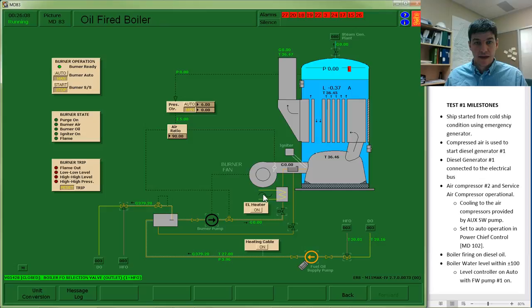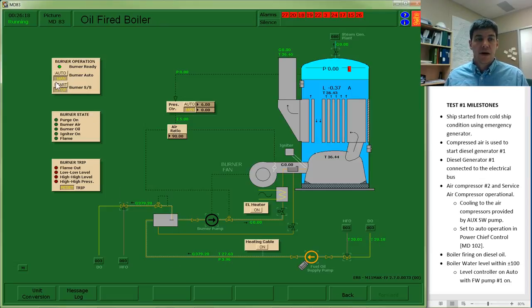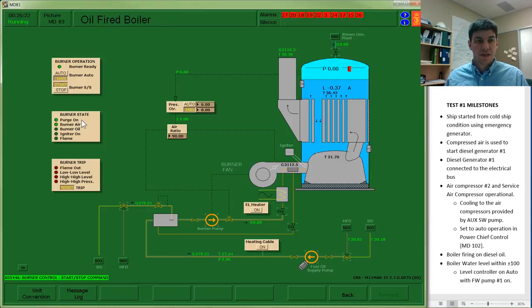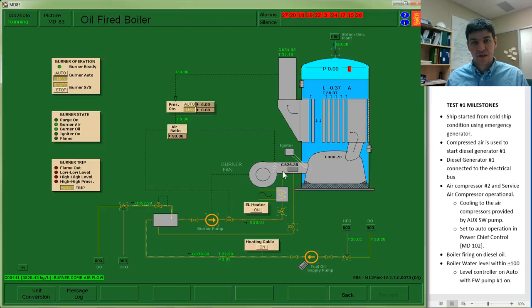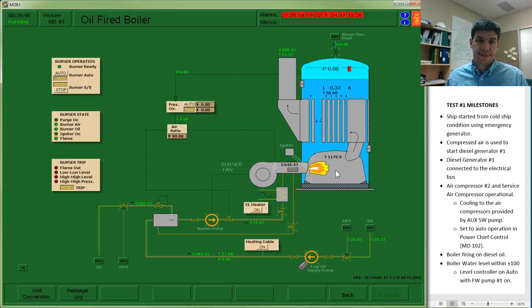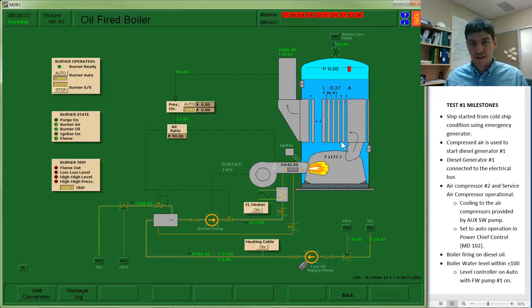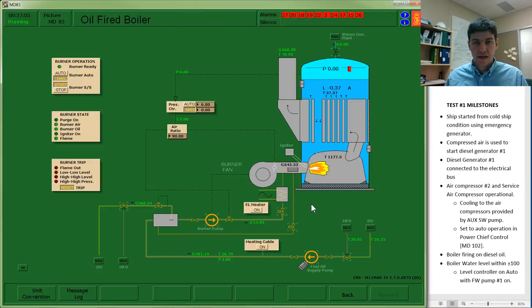Make sure when you're doing that that you don't have your heating cables on. Those are only used for the heavy fuel oil. Diesel oil doesn't require those cables on. So I hit start and it goes through, first of all, a purge process. And you can see that the flap just opened up on the fan and it's blasting through a significant amount of air through the combustion chamber. Firebox. Now the flap is closing. Fuel valves just opened up. And I just established a flame. My burner seems to be stable and operating correctly. And that was the final milestone for me to reach. So I've worked my way through and I've got all my milestones met. And I've completed this test successfully.